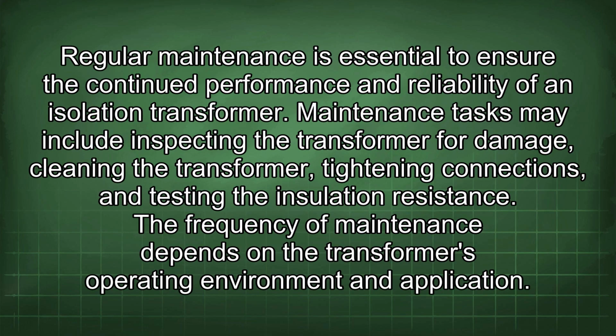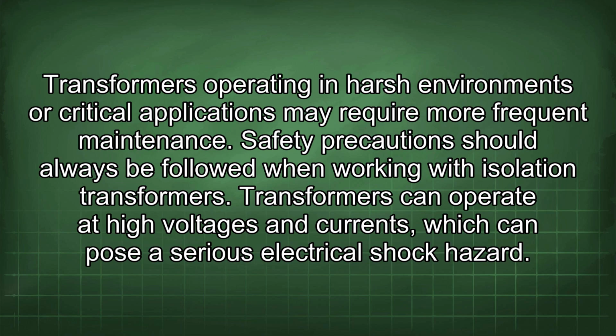Regular maintenance is essential to ensure the continued performance and reliability of an isolation transformer. Maintenance tasks may include inspecting the transformer for damage, cleaning the transformer, tightening connections, and testing the insulation resistance. The frequency of maintenance depends on the transformer's operating environment and application. Transformers operating in harsh environments or critical applications may require more frequent maintenance. Safety precautions should always be followed when working with isolation transformers.